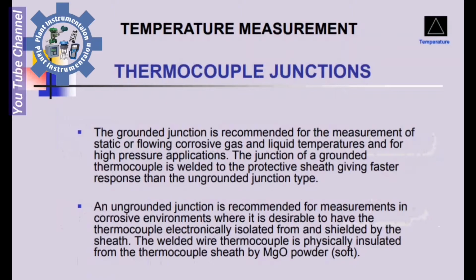Thermocouple junctions. The grounded junction is recommended for the measurement of static or flowing corrosive gas and liquid temperature, and for high pressure applications. The junction of a grounded thermocouple is welded to the protective sheath, giving faster response than the ungrounded junction type. An ungrounded junction is recommended for measurements in corrosive environments where it is desirable to have the thermocouple electrically isolated from and shielded by the sheath.